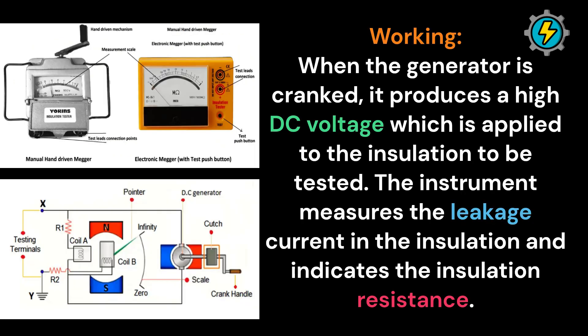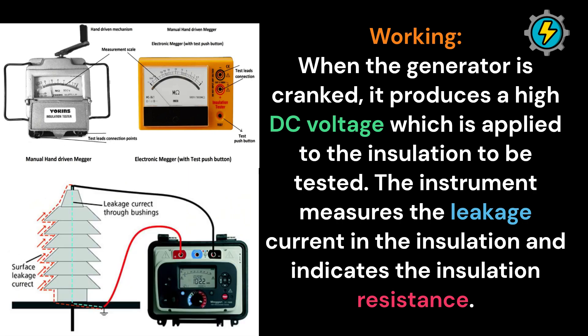Working: When the generator is cranked, it produces a high DC voltage which is applied to the insulation to be tested. The instrument measures the leakage current in the insulation and indicates the insulation resistance.